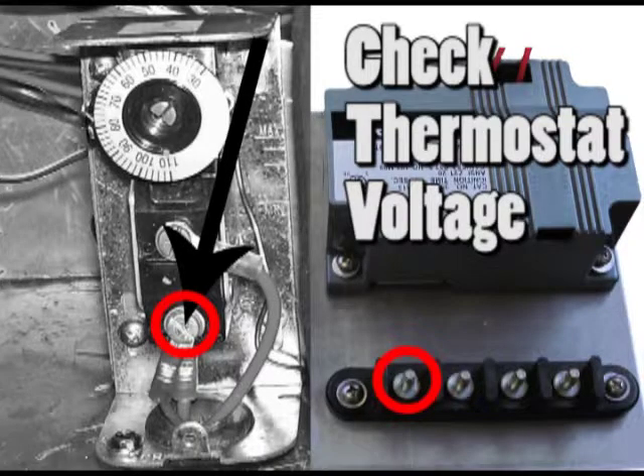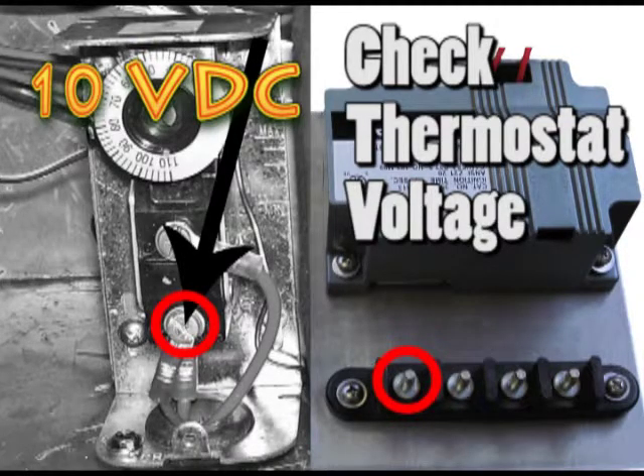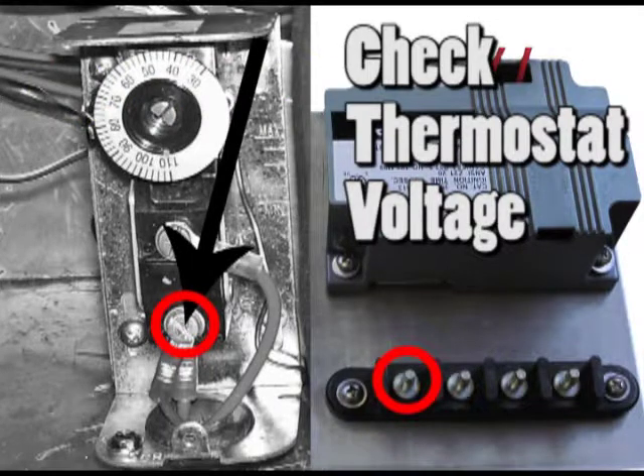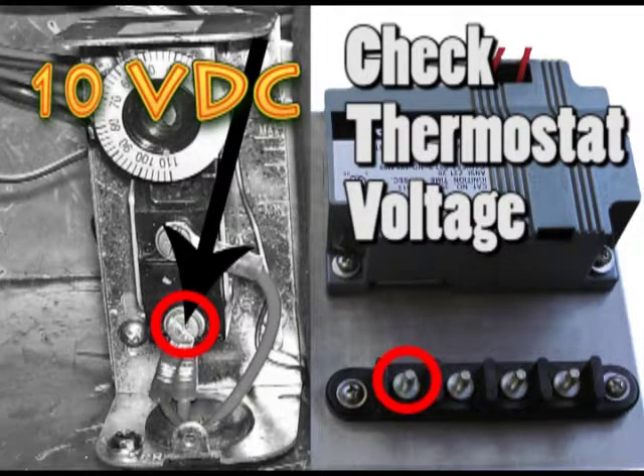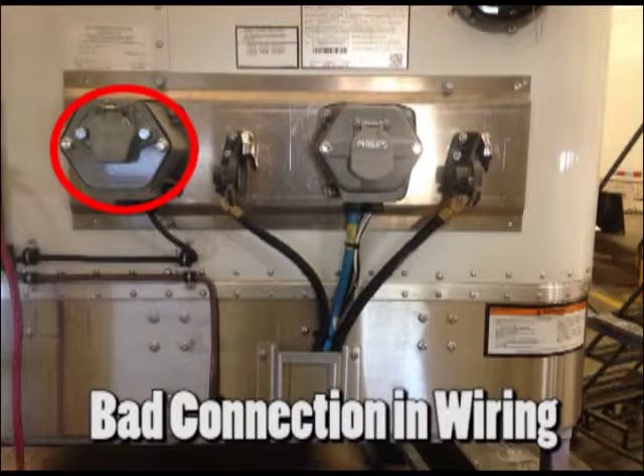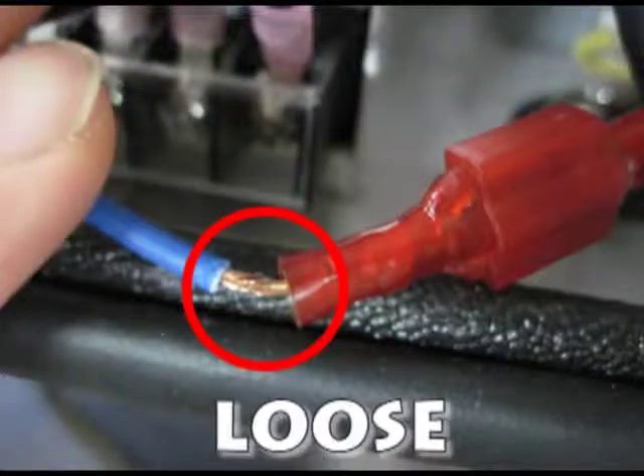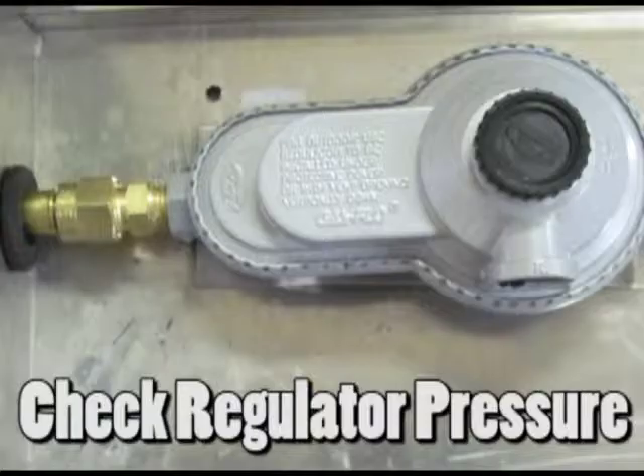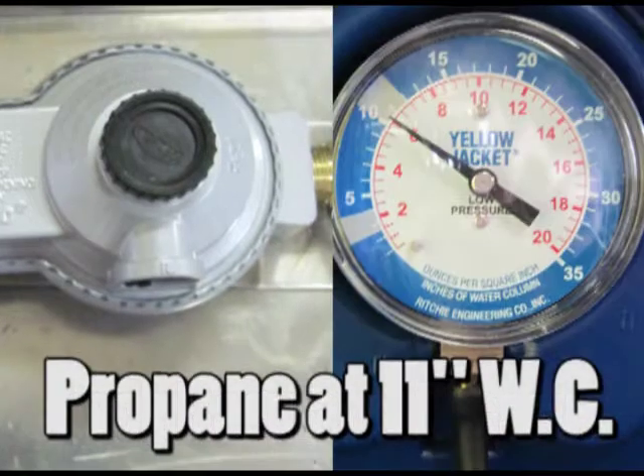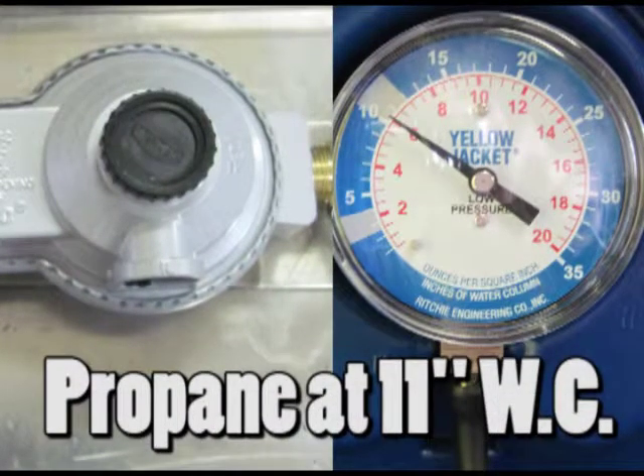Check that the heater is receiving a voltage of at least 10 volts DC at the thermostat while the blower is running. A voltage below 10 volts DC typically indicates a problem in the electrical system between the heater and the vehicle. Start looking for loose or corroded connections. Check that the regulator is producing the correct pressure of 10.5 to 11 inches of water column. This should have been done during installation.